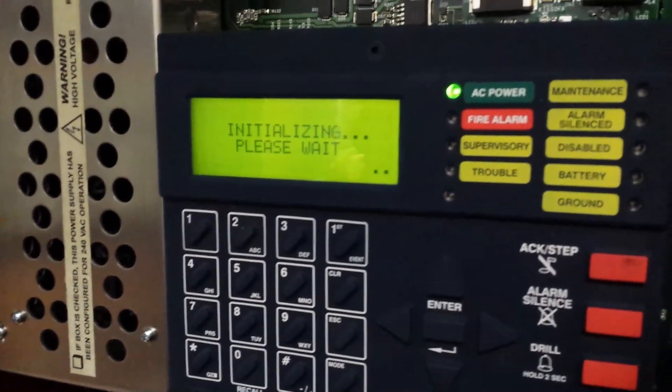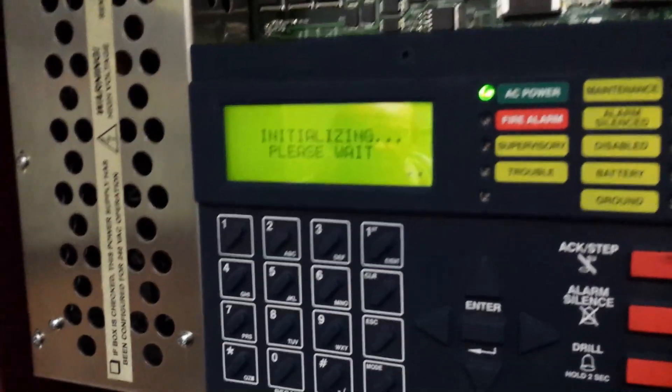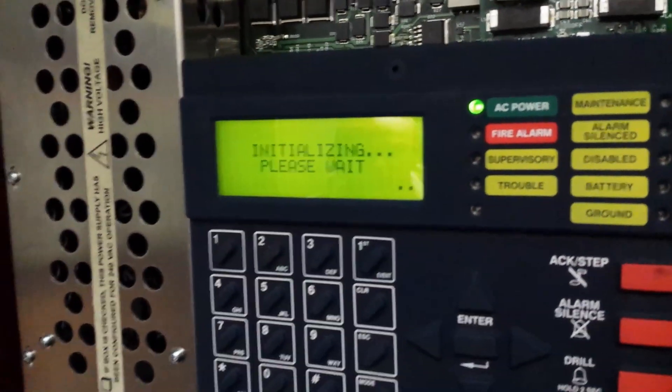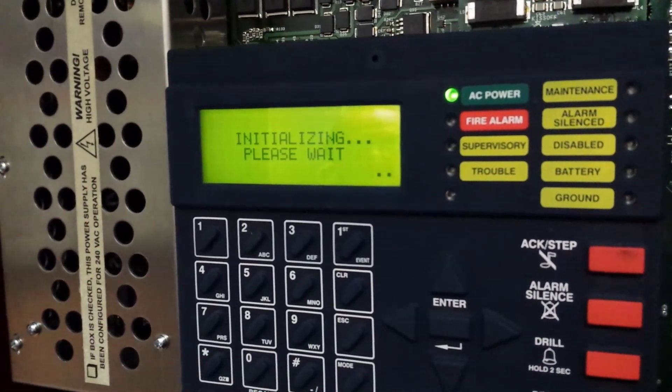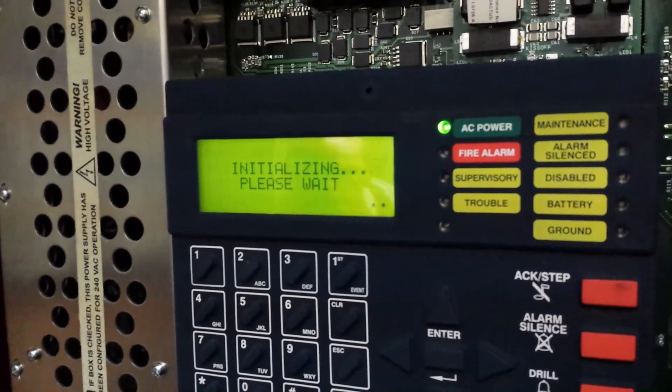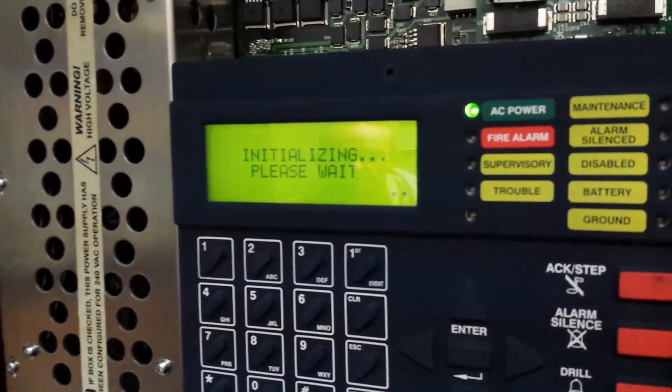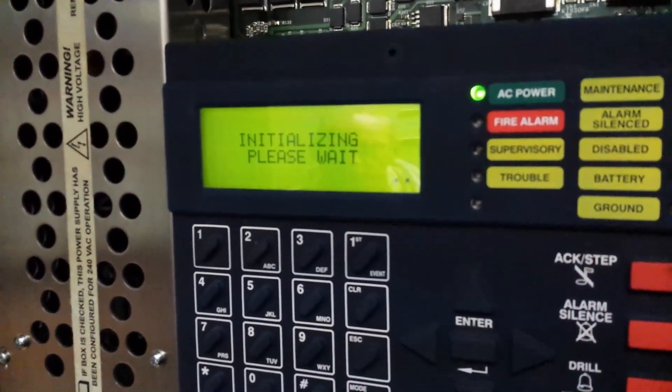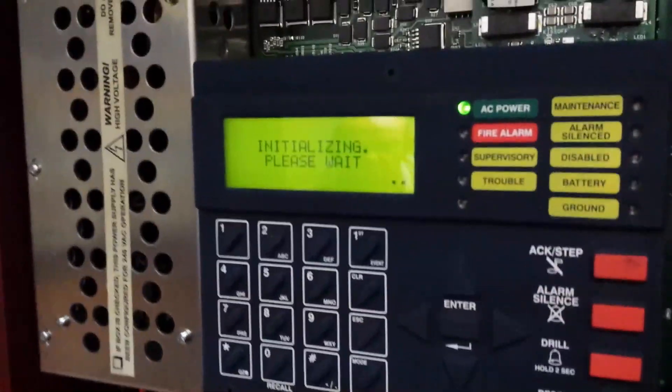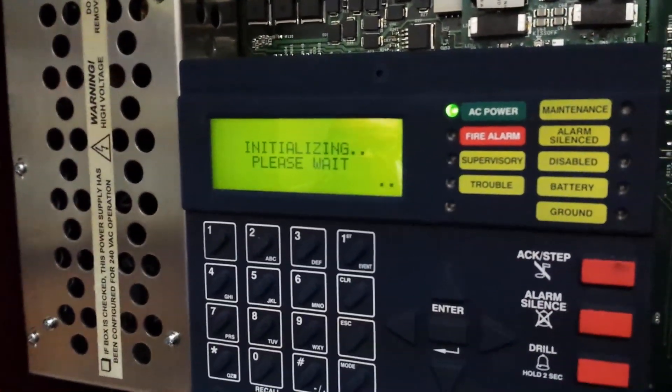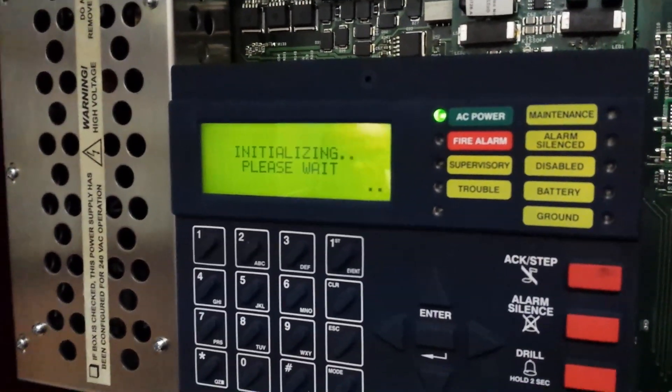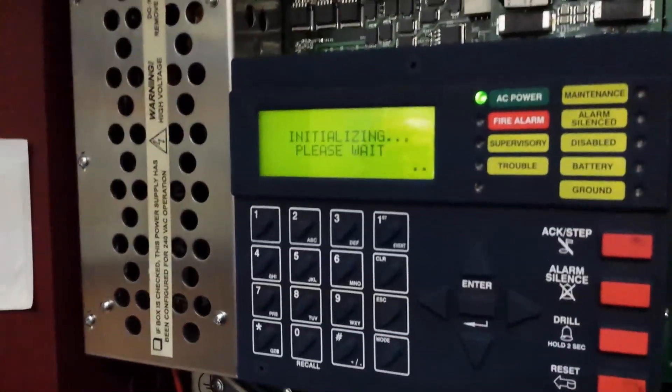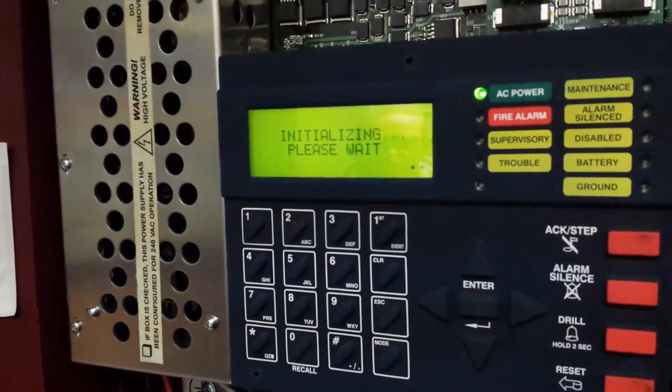We're in initializing please wait. I don't think it's going to initialize. This is what happened the other day. It seems to be now stuck in initializing please wait. We're going to go up and check the devices now and see if we do have some blinking activity. When I was resetting the pull station, there was a smoke detector that was blinking. I don't know if it's still blinking. There's definitely something funny going on here with this panel.